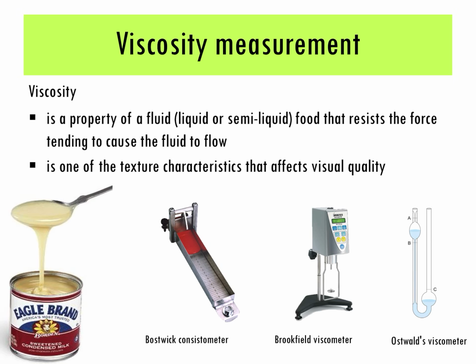And lastly, the Ostwald viscometer. We measure the time that our liquid takes to pass from point A to point B, and then we compare with the density and viscosity of water at room temperature, and then we will have an equation to calculate back how much the viscosity of our liquid of interest is. And that is an example of viscosity measurement.